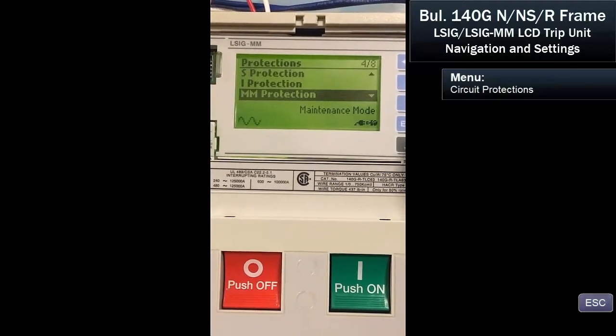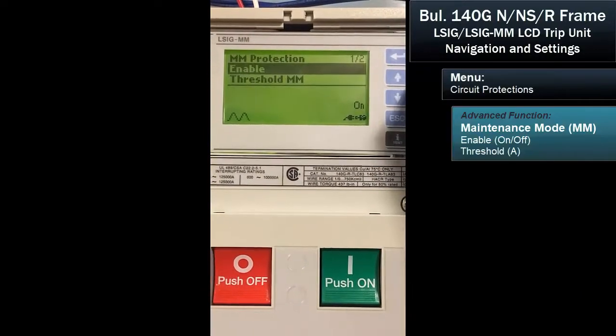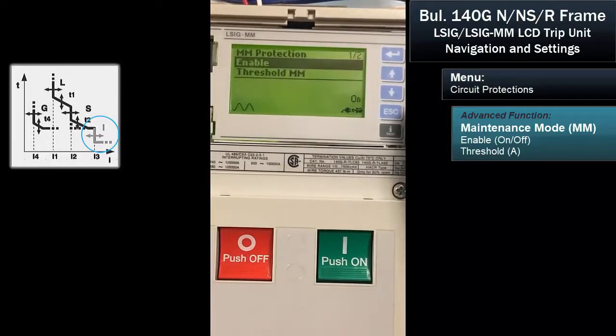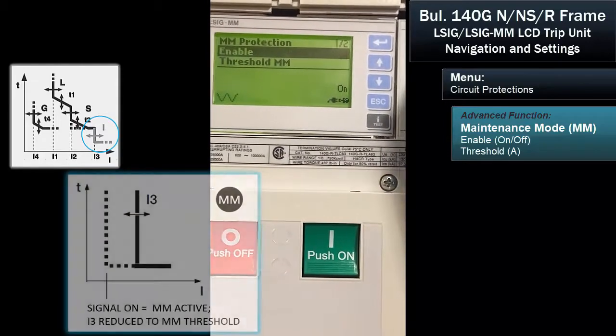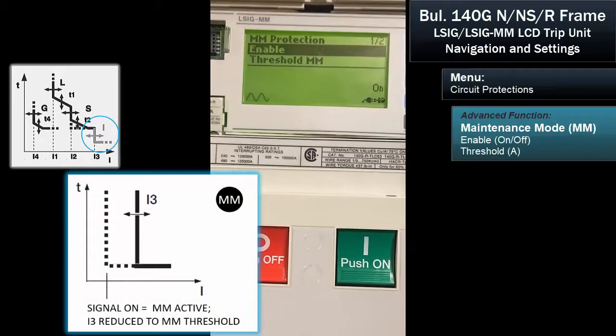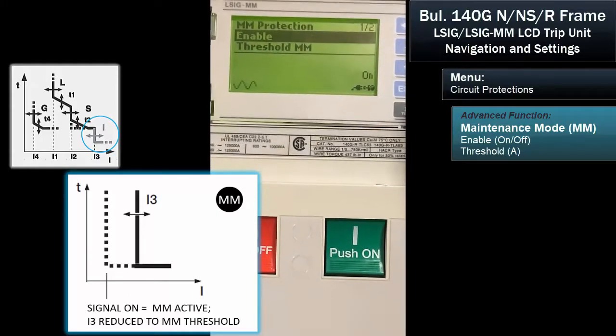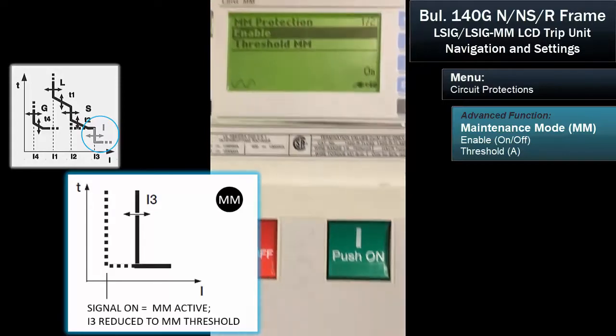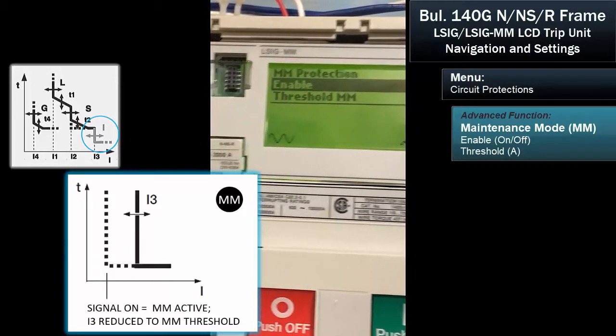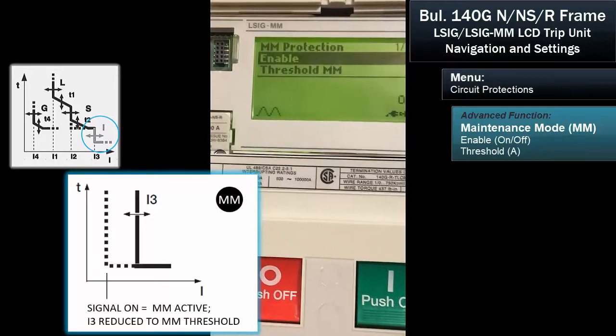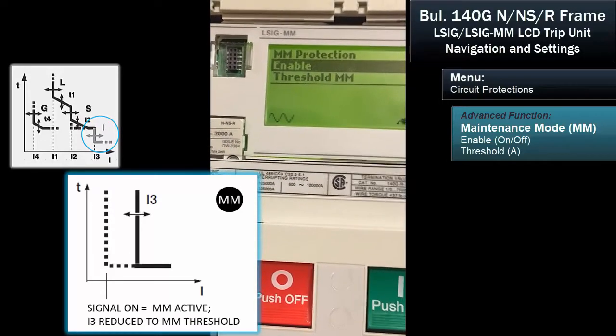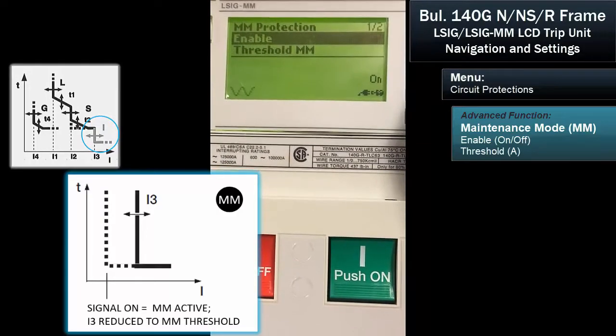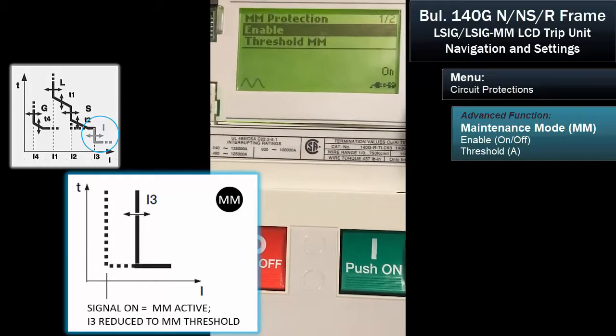Then we'll set maintenance mode. We've enabled it. Enabling maintenance mode means we've turned the breaker into a mode where an external contact closure adjusts the instantaneous trip to allow the breaker to trip faster in a situation where there's a short circuit or arcing going on downstream, reducing the amount of energy by lowering the instantaneous value.